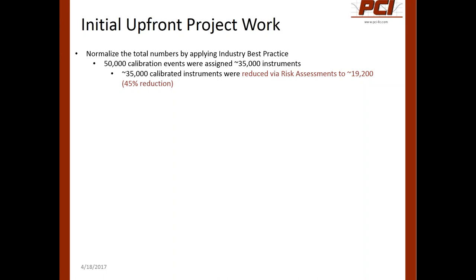The way that was done: some locations, if an instrument was located in a building that had any type of GMP process associated with it, the legacy ways of working classified everything in that building as GMP critical. So we took a risk-based approach by looking at the actual equipment within the building — was it direct impact, indirect impact, or no impact? Then, based on the impact of the equipment, we looked at the criticality of the instrumentation associated with it. That way, we knew if we had a no-impact piece of equipment, like maybe an office air handler in a GMP facility, we had no quality-critical instrumentation on it.